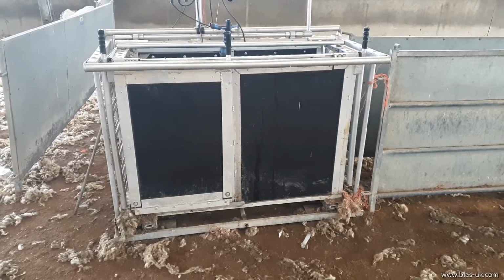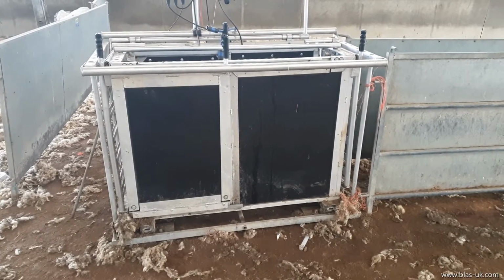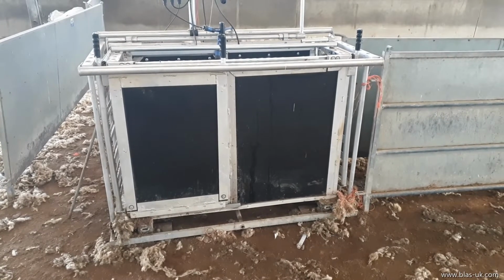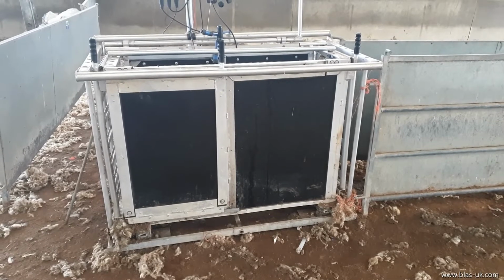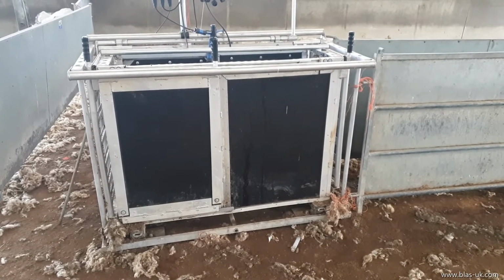If the plug caps have not been put back on the load cells when they are not in use, moisture can ingress into these, giving corrosion or an issue which does not allow the load cell to get an accurate electric reading back from the load cells. All these things combined can limit your ability to get an accurate weight. To get the most accurate weighing possible, we need to have the weigh crate on the levelest, firmest ground possible. I know this is sometimes difficult, but if we're trying to get more accurate weights, we need to look at this.